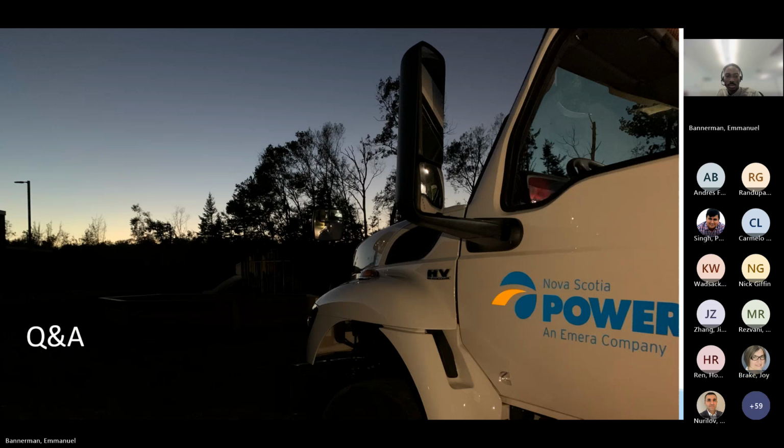But the recommendation here is get the best model you can, because it's going to give the best results. When you get into looking at control interactions and high frequency damping, those type of issues, when we match against field data, we're matching against field data today, which is not a high IBR grid. What we do is we match the system we have today till it matches the case that we're running today.